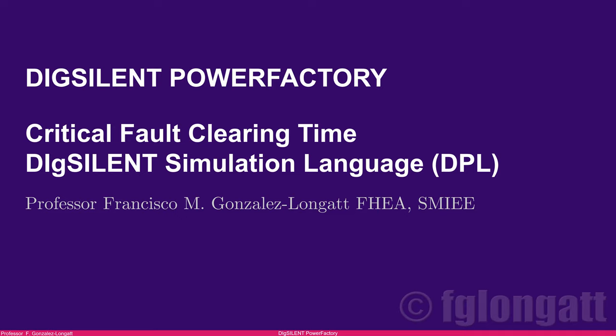To be honest, this DPL is extremely simple. What it does is apply a short circuit to the project, to the power system, and then remove the fault, and then assess the time domain response, the time series representing the rotor angle. From there, it is able to identify if the system is stable or not. The idea is that this DPL uses a systematic approach to obtain the critical clearing time. That is basically the idea of this video.